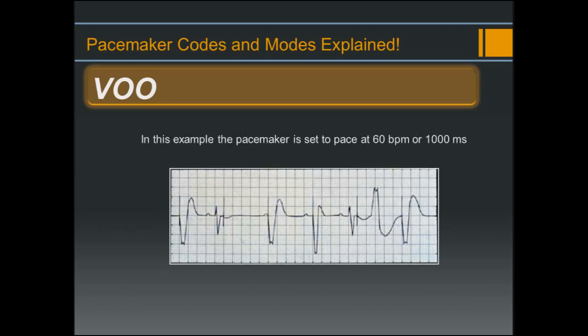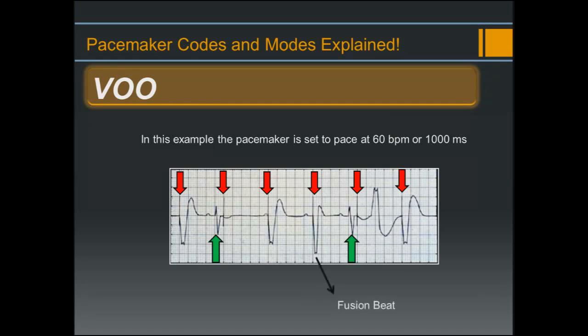In this example, the pacemaker is set to pace in VOO at 60 beats per minute, or every 1000 milliseconds. Here we see a pacing pulse that captures the heart, giving us a wide QRS morphology. Next we see an intrinsic QRS — since the pacemaker's sensing is turned off, it is unable to sense this intrinsic event and therefore paces again 1000 milliseconds after the first pacing pulse. It will continue to pace every 1000 milliseconds with total disregard for what the heart's intrinsic rate is.